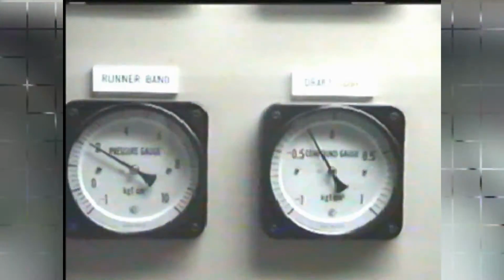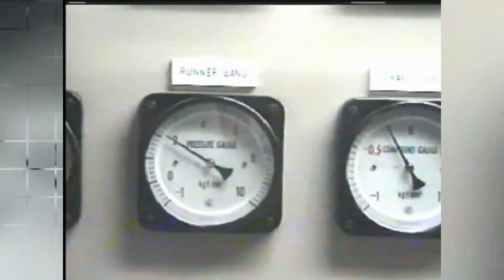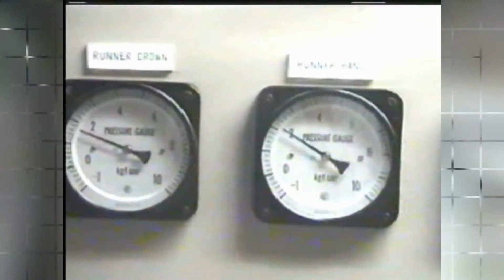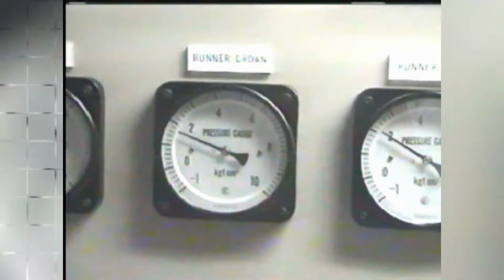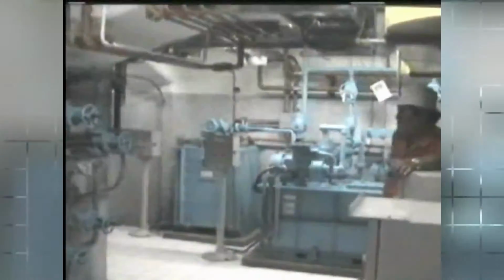The governor is suitable for manual control at the governor cabinet and for remote electrical control of the turbine from the main control panel in the control room. It shall also be suitable for automatic synchronizing. The turbine control panel consists of group status indicator, group fault indicator, solenoid valves, limit switches, auxiliary relays, pressure gauges, dial-type thermometers, pressure actuated switches, control switches, etc.